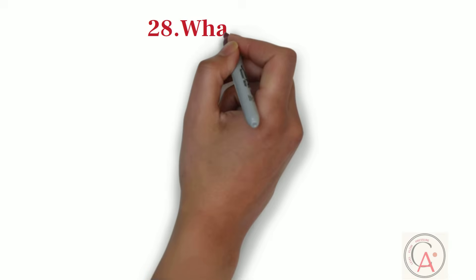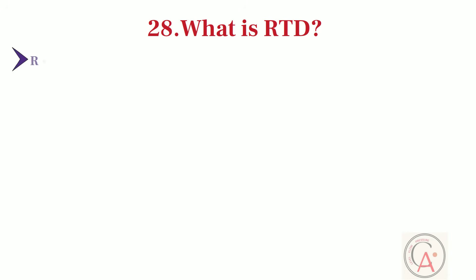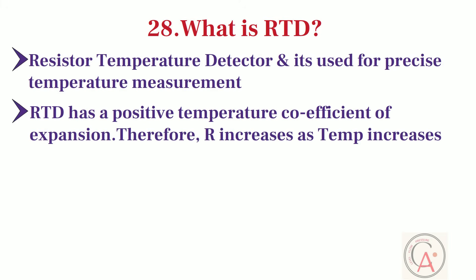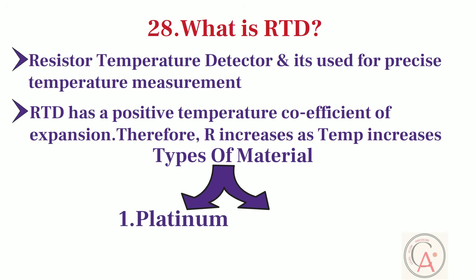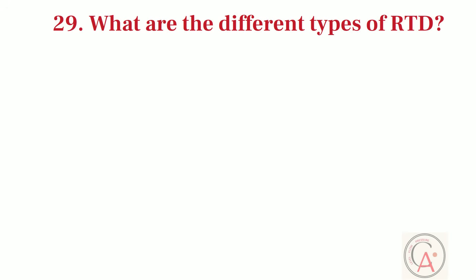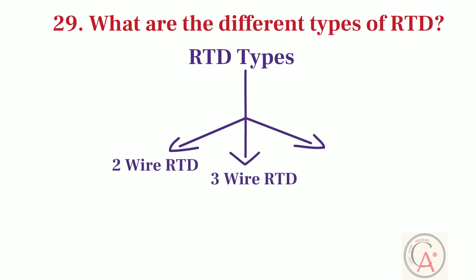Next question is, what is the RTD? RTD is resistor temperature detector, and it is generally used for precise temperature measurement. RTD has positive temperature coefficient of expansion. It means resistance of RTD increases when the temperature increases. Based on material, RTD has two types. First type is platinum. And second type is nickel. Second last question is, what are the different types of RTD available in the market? There are mainly three different types of RTD. First type of RTD is a two-wire RTD. Second type of RTD is a three-wire RTD. And third type is four-wire RTD.